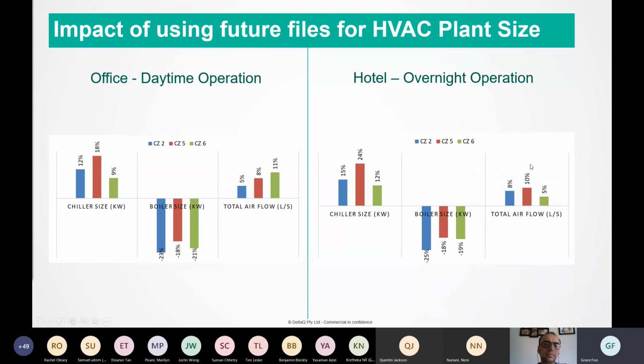The main takeaway from this is that our chiller size or cooling capacity required roughly increases by between, call it, 10 to 20%. Okay. In hotels, we see that climate zone 5, which is sort of your Sydney in this case, because that's what we modeled, increases by up to 24%. Boiler size or heating capacity reduces by about 20%. And then total airflow, so that's where your air handling plants, your ductwork risers, increases by between 5 to 10%.